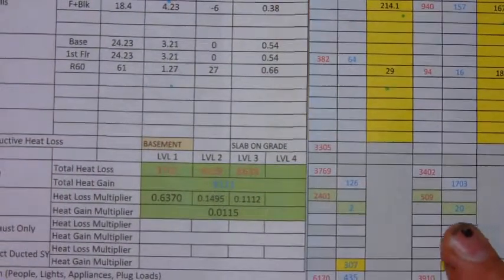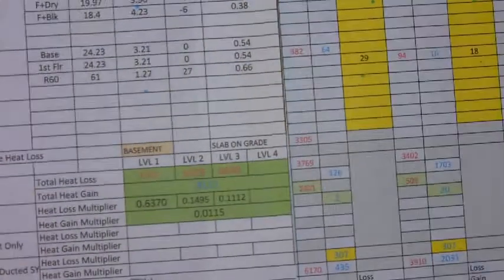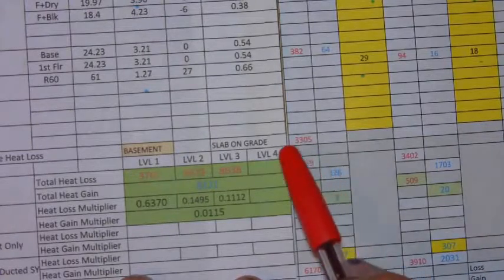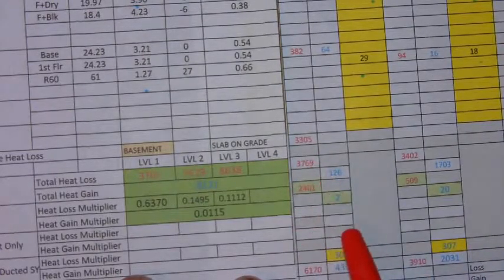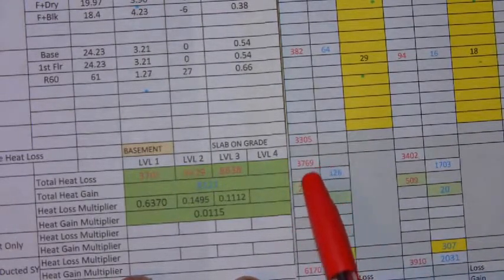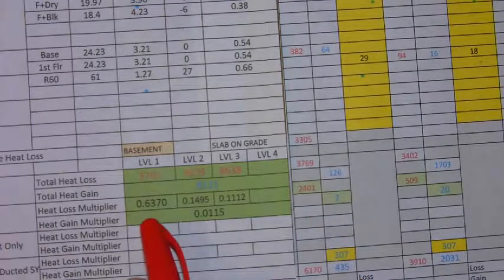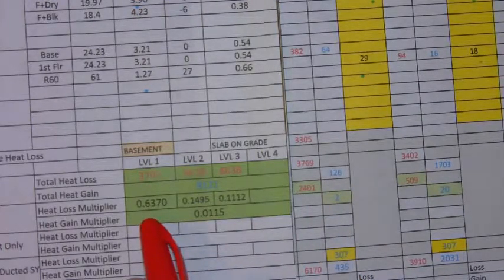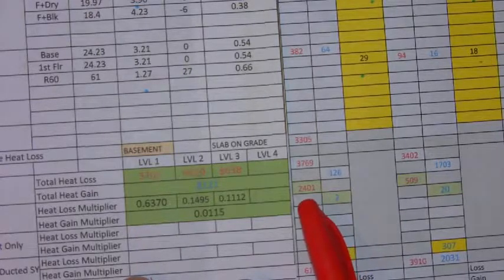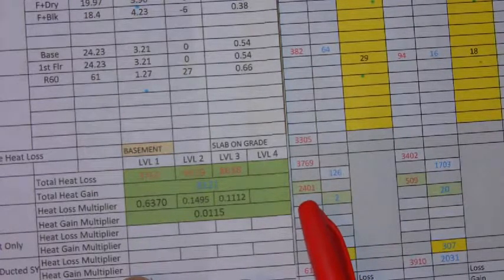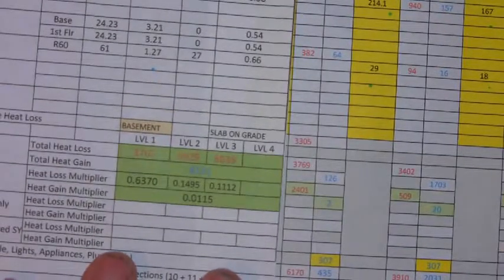So, if we look at the basement, this is the total heat loss for the basement. So 3769 times the multiplier 0.6370 equals 2401. This is the amount of air leakage that we will get in the basement.